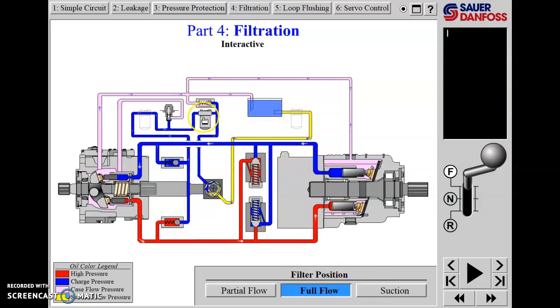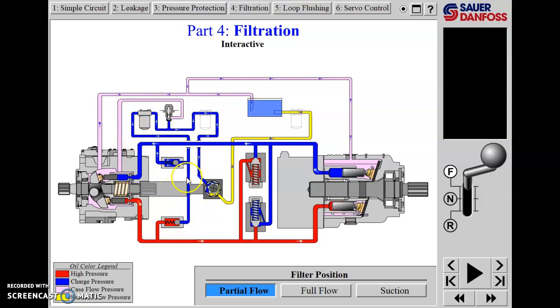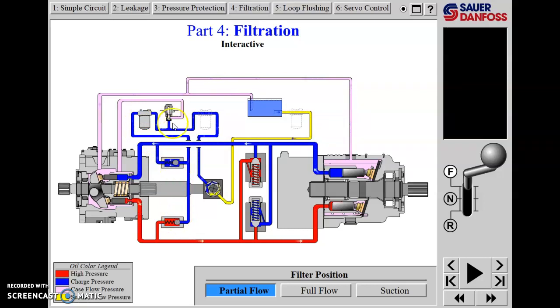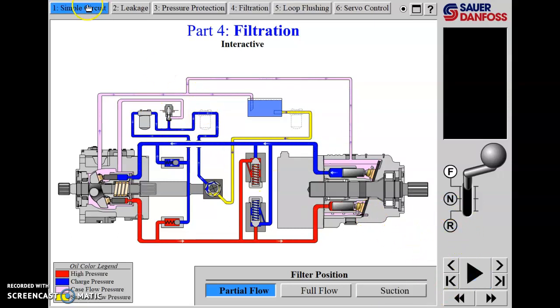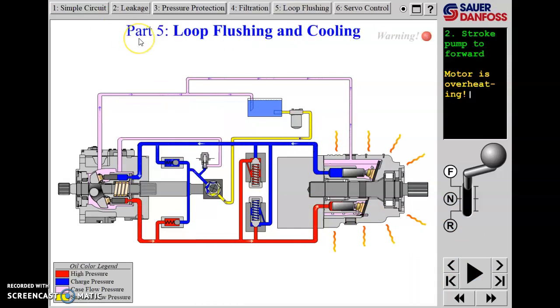This suction location is less common on mobile equipment but is found in industrial hydrostatic systems inside heated buildings. To review: we've got the suction location, a full flow location with a filter relief installed, and a partial flow location where only the oil literally going into the charge loop gets filtered. That's really the only necessity — we only need clean oil entering the drive loop — so partial flow is probably the best and simplest location for heavy equipment, since the charge relief handles pressure protection.